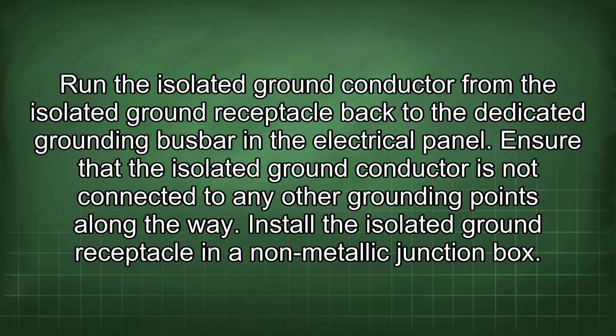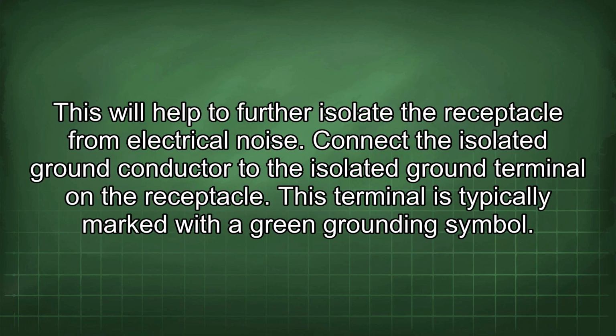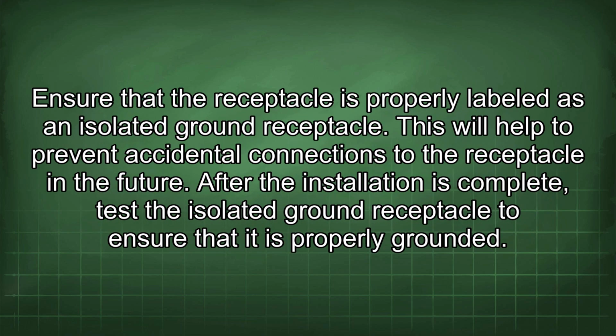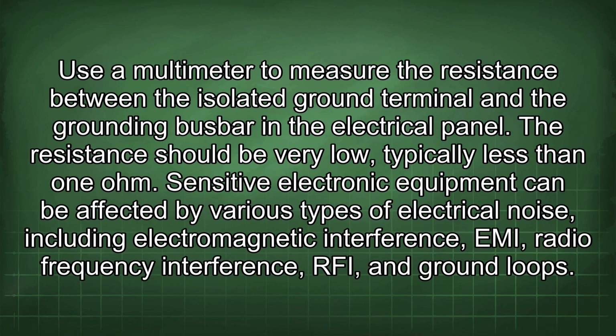Install the isolated ground receptacle in a non-metallic junction box. This will help to further isolate the receptacle from electrical noise. Connect the isolated ground conductor to the isolated ground terminal on the receptacle. This terminal is typically marked with a green grounding symbol. Ensure that the receptacle is properly labeled as an isolated ground receptacle. This will help to prevent accidental connections to the receptacle in the future. After the installation is complete, test the isolated ground receptacle to ensure that it is properly grounded. Use a multimeter to measure the resistance between the isolated ground terminal and the grounding busbar in the electrical panel. The resistance should be very low, typically less than 1 ohm.